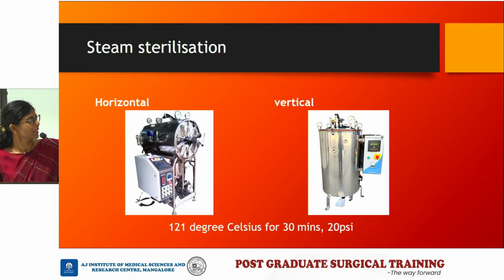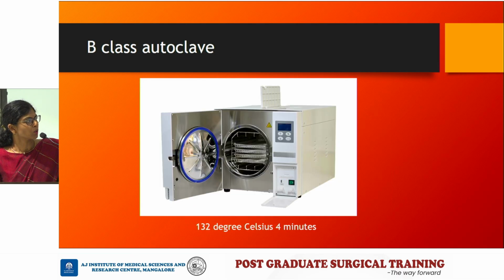So just for completion's sake, these are gravity-dependent autoclaves. Most of the OTs have these horizontal autoclaves or the vertical autoclaves. Basically, what is done is steam is pumped into the chamber, which will push the air out. So it takes some time for the air to completely come out. And then a temperature of around 121 degrees Celsius is achieved for about 30 minutes at 20 psi. So this is the usual steam sterilization that is done. You have a quicker way of doing it, and this is called a B-class autoclave. The only additional thing is that it has a pre-vacuum setting. So it will remove all the air automatically. So obviously the autoclave time comes down to around 4 to 5 minutes, which is much easier.